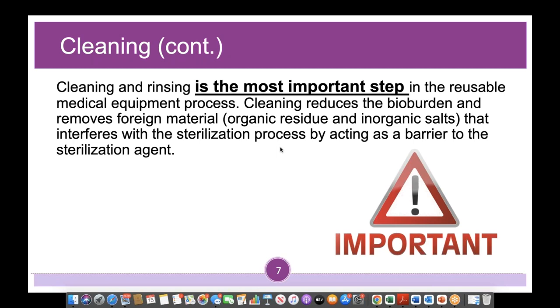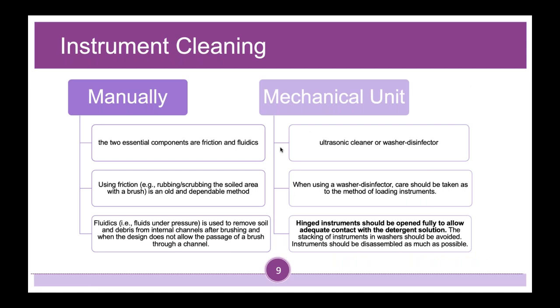Instrument cleaning has manual and mechanical components. For manual cleaning, the two essential components are friction and fluidics. Using friction—rubbing, scrubbing the soiled area with a brush—is an old and dependable method. Fluidics is fluids under pressure, used to remove soil and debris from internal channels after brushing, and when the design does not allow the passage of a brush through a channel.